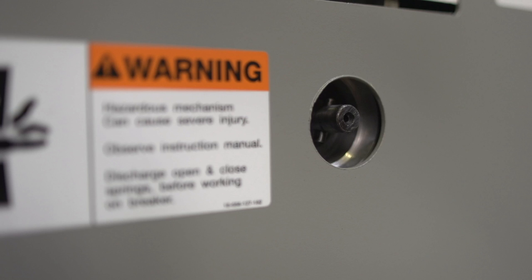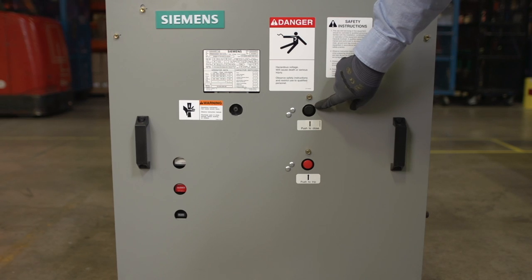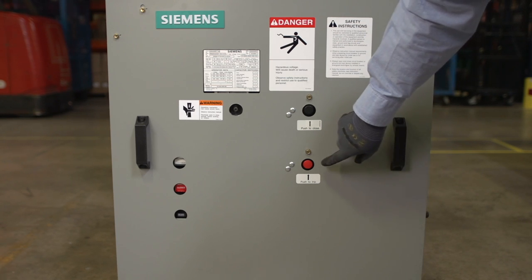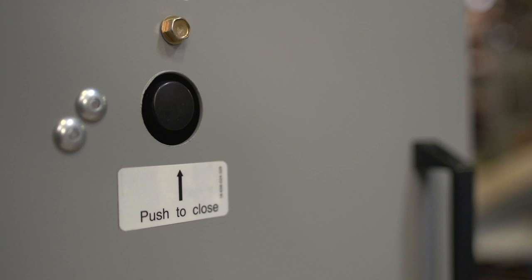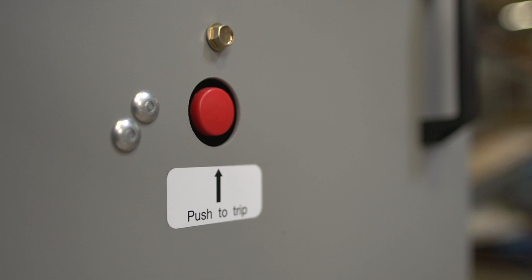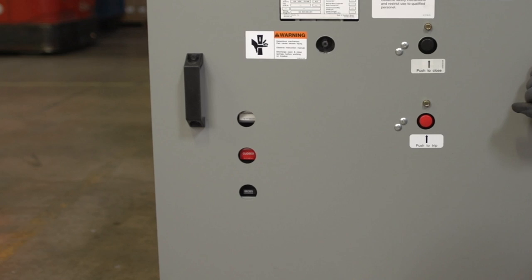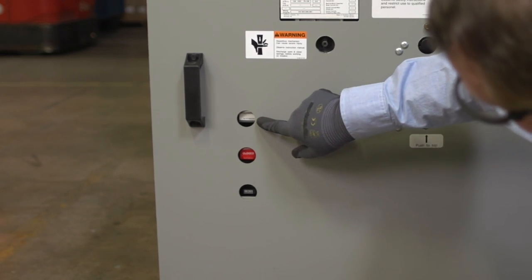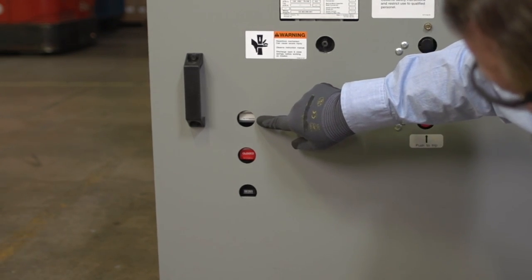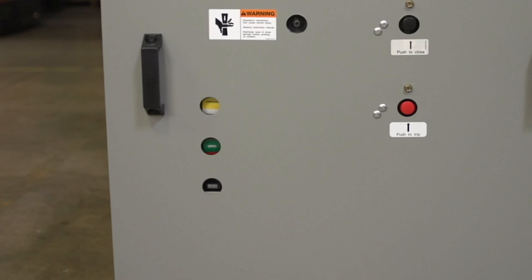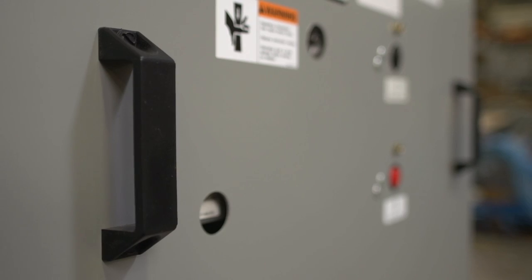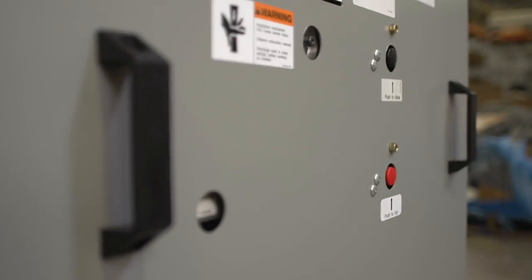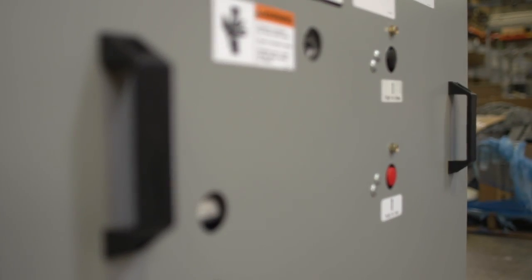This is where the charging handle is connected to charge the closing springs in the circuit breaker. These are the push to close and push to trip buttons. Both are colored according to ANSI standards. On the left side of this panel is the spring charge status indicator, which is either charged or discharged. Here is the operations counter for the circuit breaker. Remember, Siemens medium voltage circuit breakers are tested in the factory, so it's normal for a brand new circuit breaker to show 250 to 300 operations on this counter. And finally, these handles help move the circuit breaker into and out of the cell.